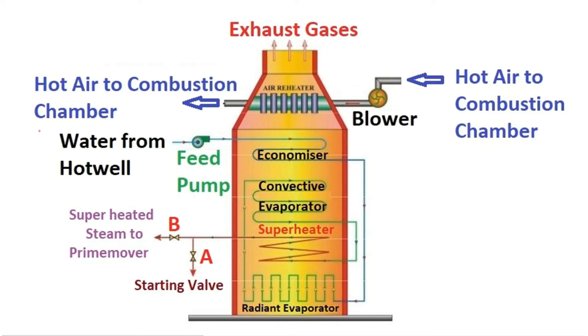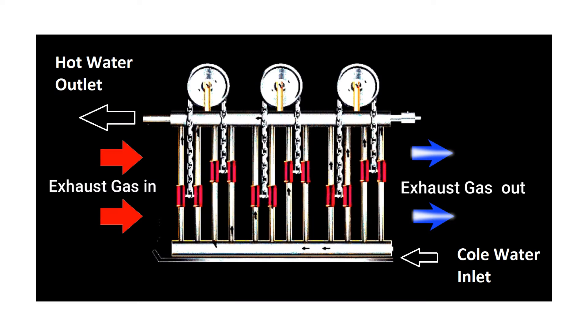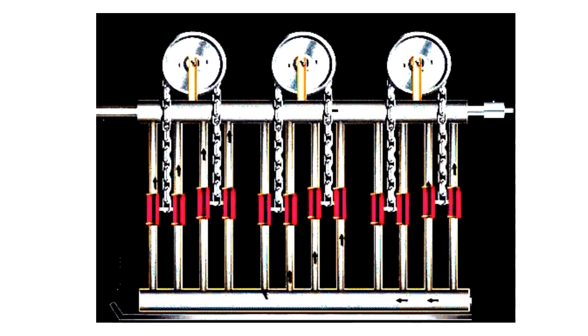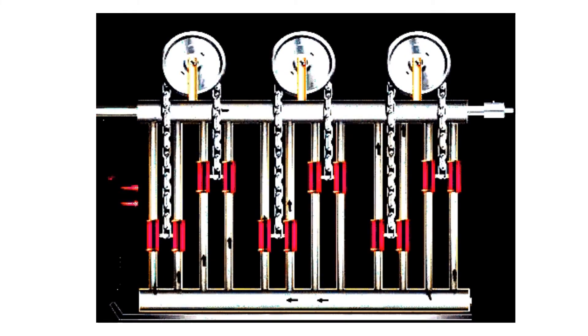The water is first passed through the economizer. The economizer is an accessory that saves fuel and increases the performance of the boiler. Flue gases pass through the economizer coil before entering the chimney. Some amount of energy available in the flue gases is utilized to transfer heat to the water through the economizer coil.